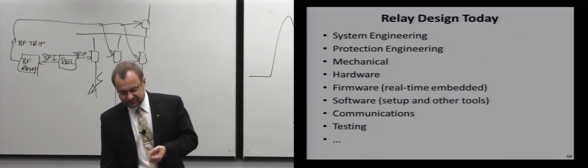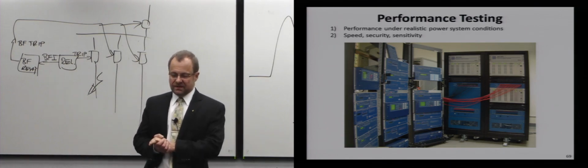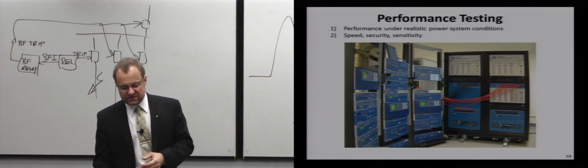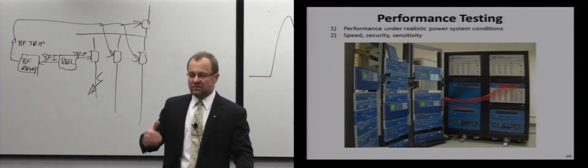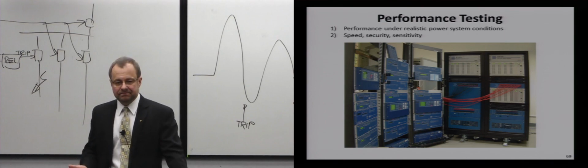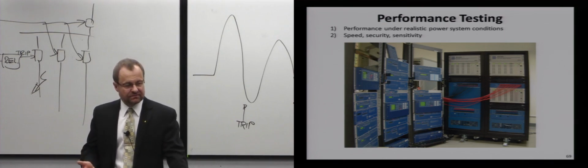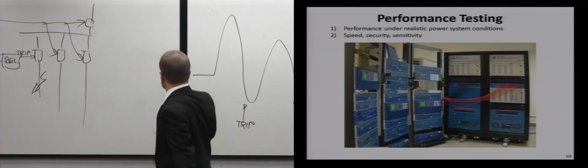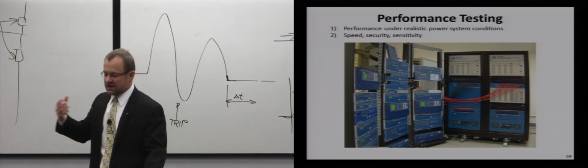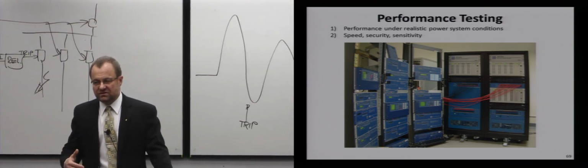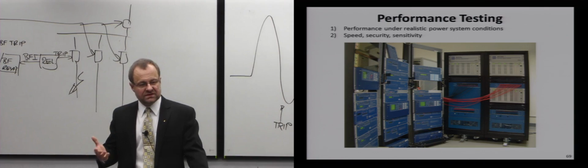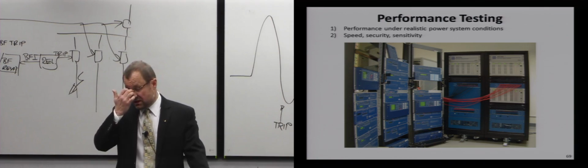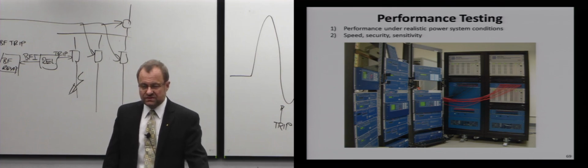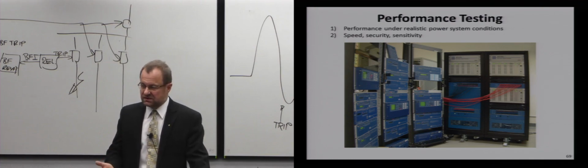There is testing. A few words on testing. So there are a couple of types of tests that we do. One is performance testing. And what performance means is, we build a distance relay. How well does it do distance protection? So you expose it to realistically looking currents and voltages, different lines, different operating conditions, different sources of errors, things like CT saturation or errors in the voltage transformers. And you want to see what's the speed, what's the sensitivity, what's the security. Is it going to misoperate? How accurate is it, being fast, and so on.